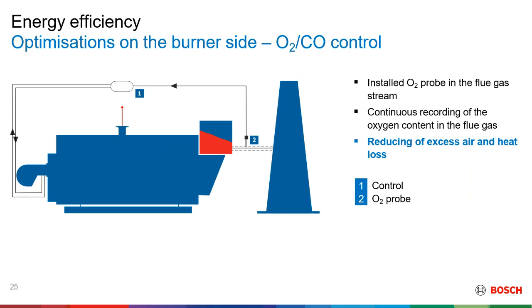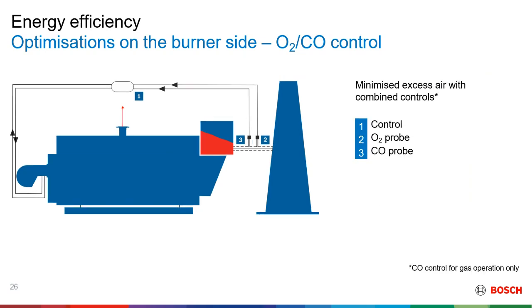Okay. So here is an illustration showing how a setup with an O2 control would look. You will have a probe after the economizer before the flue gas flows into the chimney. You will have a control probe which will send signals to the burner, and this is how a setup for O2 control would look. On the next slide, you'll see a setup with both O2 and CO control. Here you'll have two probes in the connection between the chimney or the stack and the economizer. The probes will be able to monitor the amount of excess oxygen and CO in the flue gas and correct the burner curves respectively. Okay.